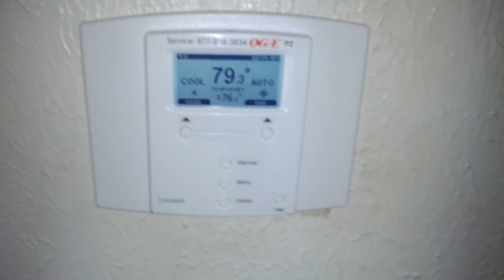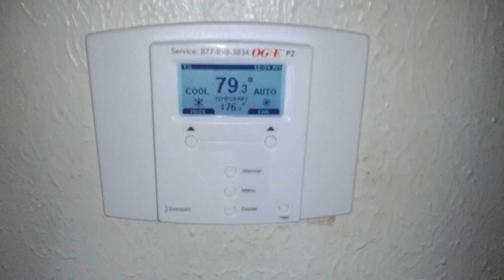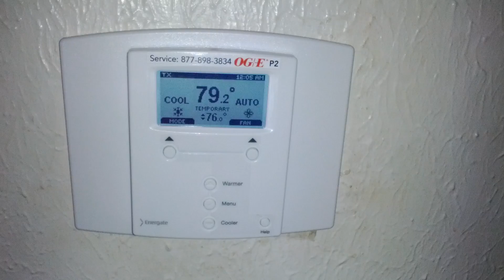So it definitely, I think, that's what it is. It tries to draw too much power off the transformer, thus it reboots. So OG&E needs to take some advisement on this and upgrade the transformers in the furnace units as well as these things. Whenever they install this, it needs to be upgraded. Transformer needs to be upgraded as well as the thermostat.